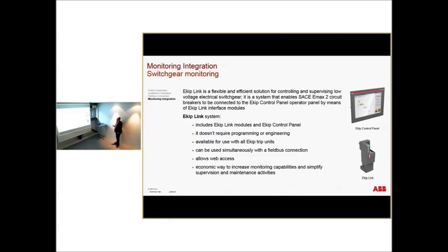The Ekip Link system is, there are some requirements in the market that say, I don't want to operate in front of the breaker itself. I could be electrocuted, there could be an arc, there could be many other things. I want something 5 meters, 3 meters behind. So in this case, I want something that operates remotely the breaker, but I don't need the communication. So this is also a faster system.